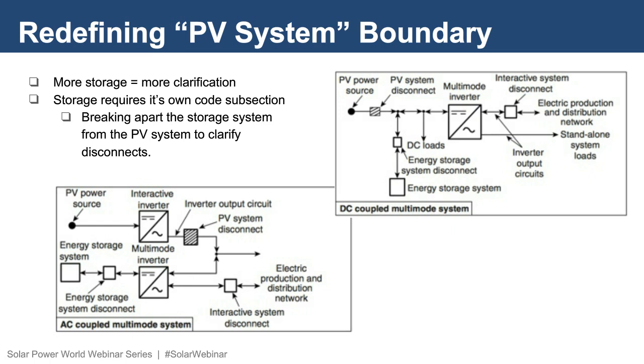Two examples of PV system boundaries, where the PV system disconnect is located and the PV system is coupled, are shown above. The first is a DC coupled system and the second an AC coupled system. In both cases, there is energy storage present, which NEC 706 would encompass. In the DC coupled system, the PV system boundary would be considered the PV system disconnect. In the AC coupled system, the PV boundary would be considered the AC disconnect on the output of the interactive inverter, which would be the same as in a purely interactive system.